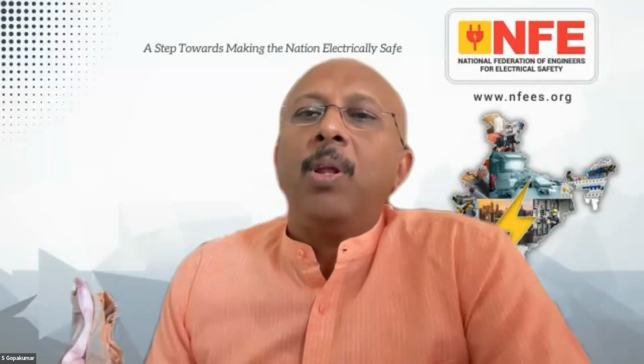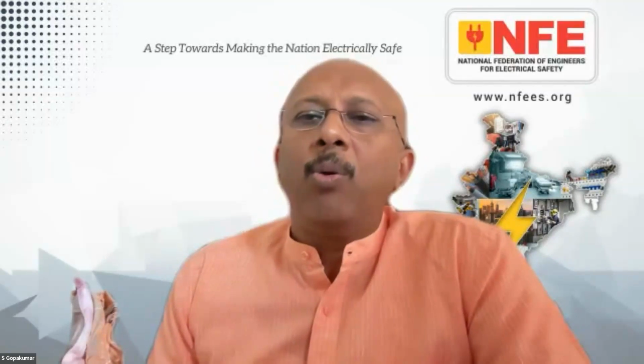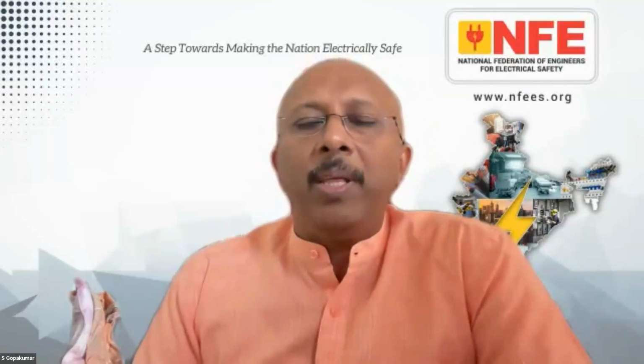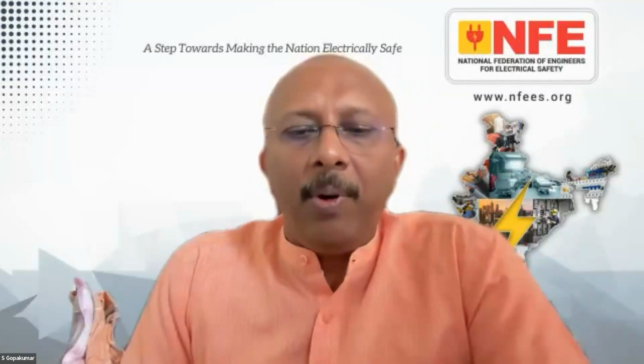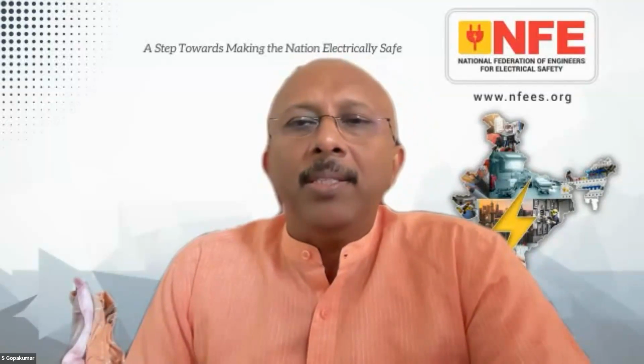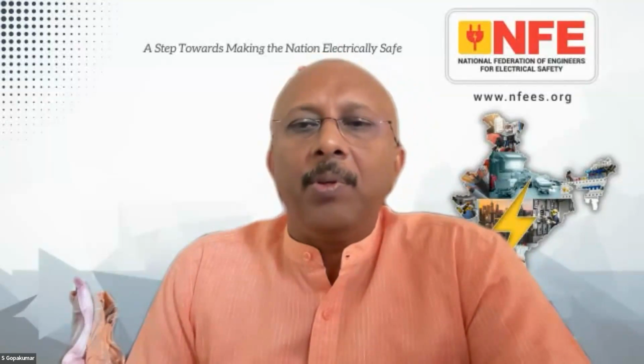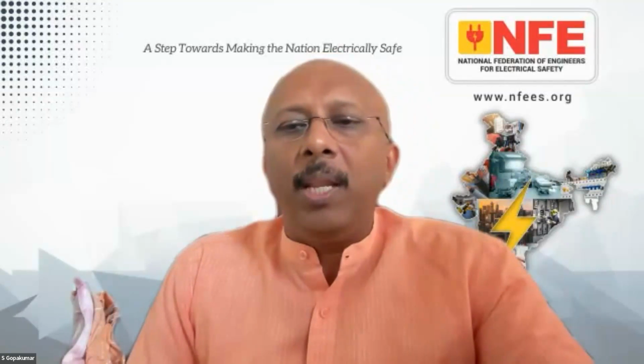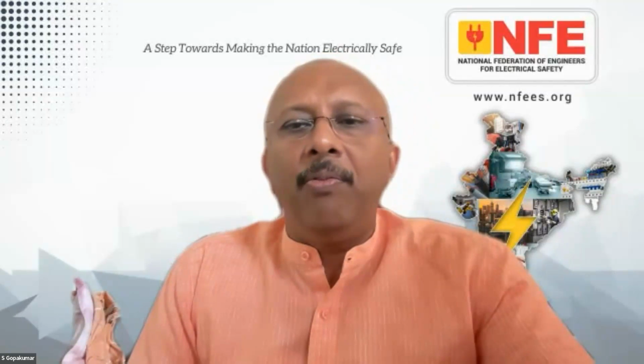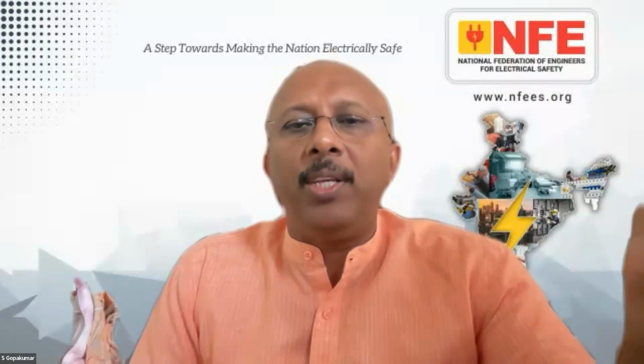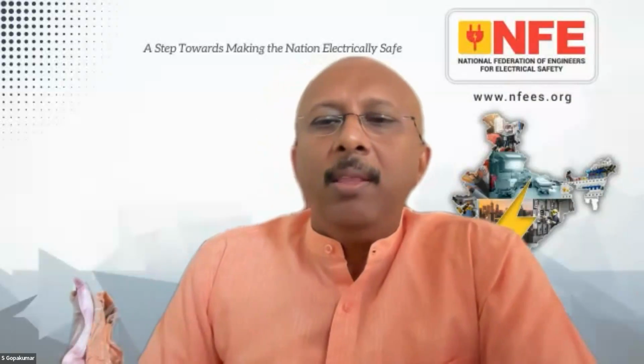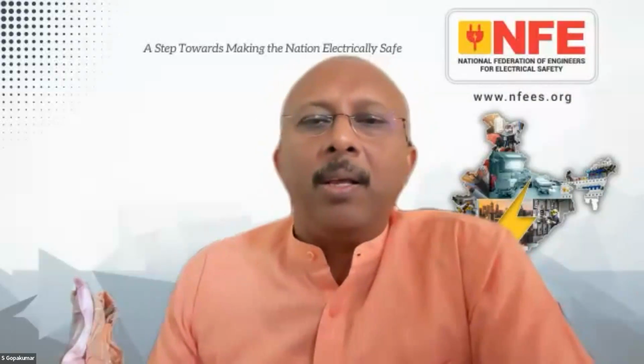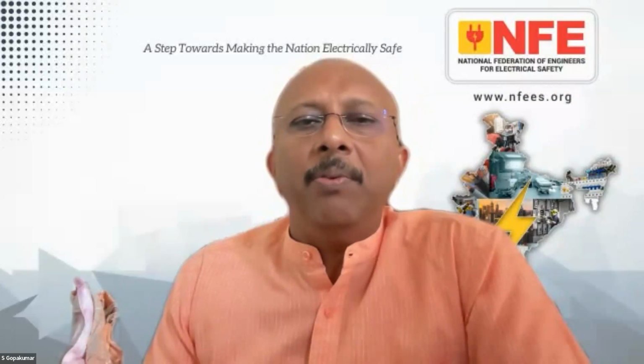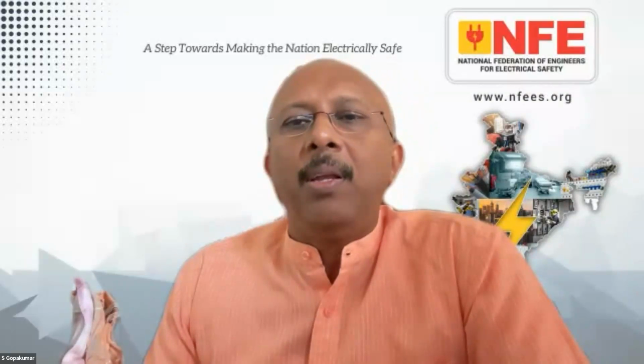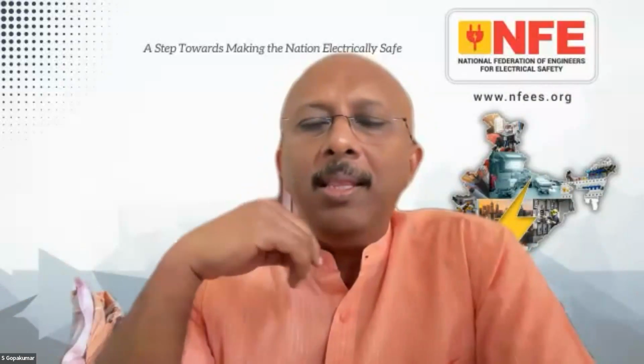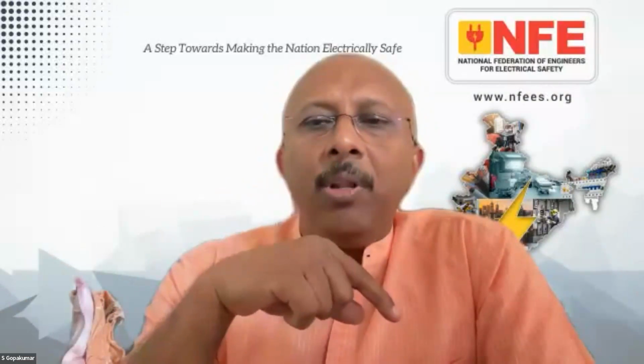Again, fault loop impedance. What are the test methods to do a fault loop impedance test? As Mr. Nitin told, please note that there are meters available. Normally, the meters are called multi-function meters. So you have to buy the meter. Then the instructions are there. You have to connect it between phase and the earth. Then you put it into the test mode. It tells you the fault current available in that particular circuit. Then you have to compare it with the MCB which you are using. It's very simple.